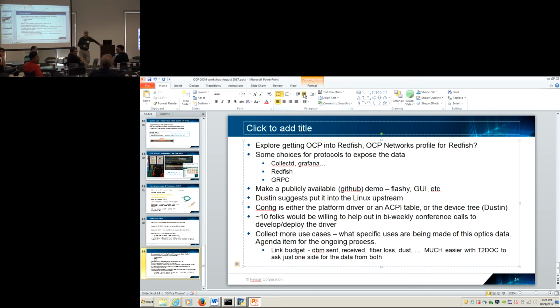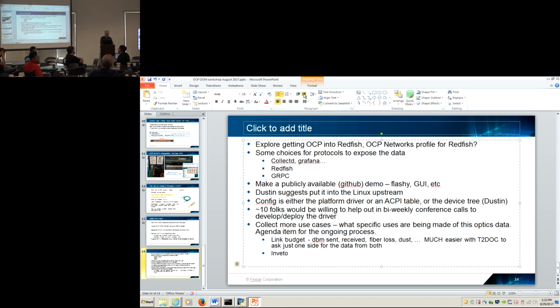So for use cases, you have an inventory. You can do an initial inventory that includes all the optical characteristics upon deployment, and then you can continue to monitor whether those operational statistics change. For instance, you can detect whether a fan is beginning to fail. You could use the system monitoring of fan speed, or you could use the temperature of the module to detect that the fan is failing. So basically inventory and monitoring.